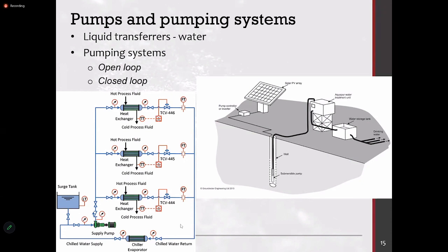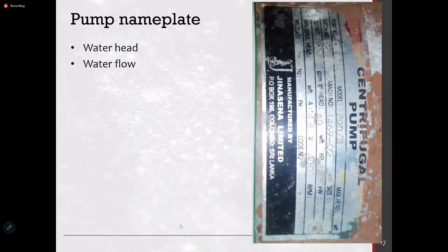and the pump capacity can be saved, and in the network you can cut down the demand for the pump power. So that is a key thing. Most apartment buildings have very big, high capacity pumps to ensure that they only run one or two times a day. So the entire day's consumption is filled in 15-20 minutes, which is a very high flow rate. But I rather recommend you go for a low flow rate, or match the flow rate of the consumption. You can make it a little bit higher, so you fill up the tank quite slowly. That will reduce your demand charge. The kWh energy will not be different, but your demand can be reduced by reducing the flow rate.